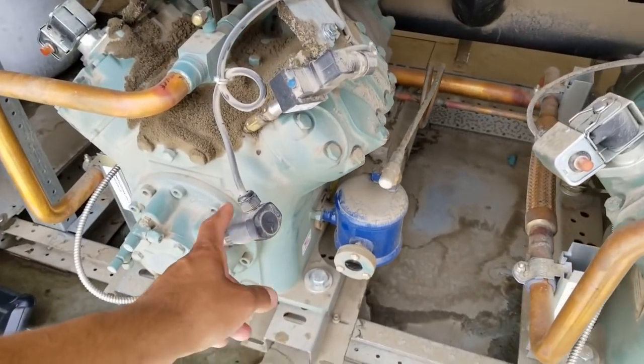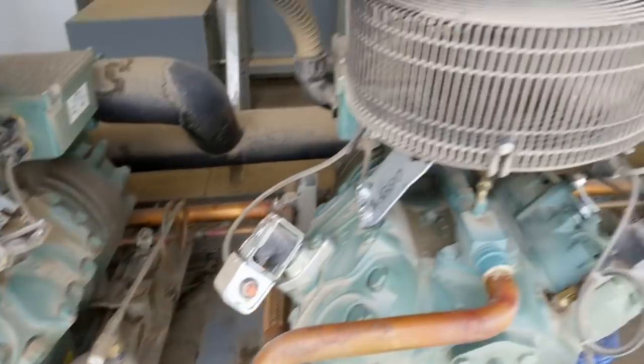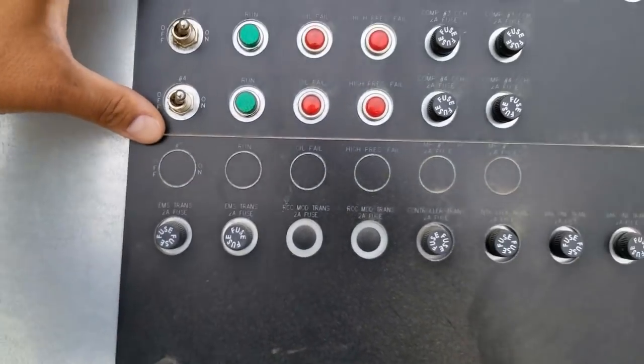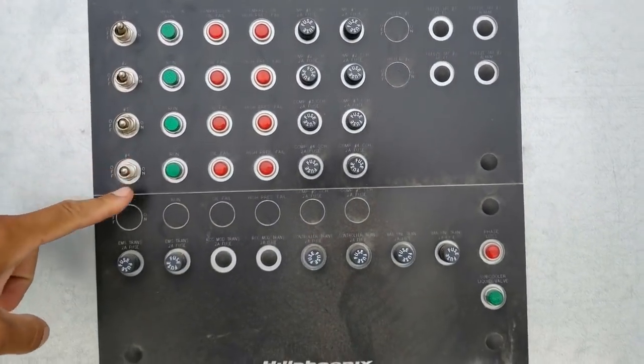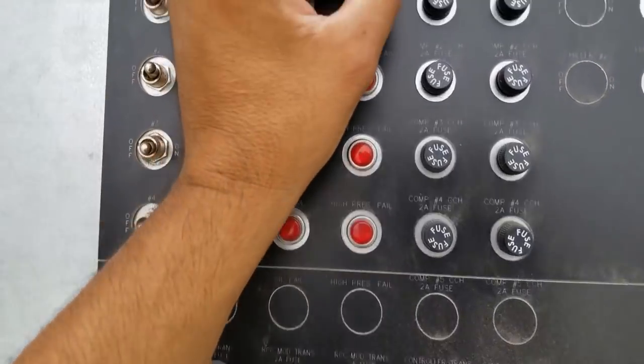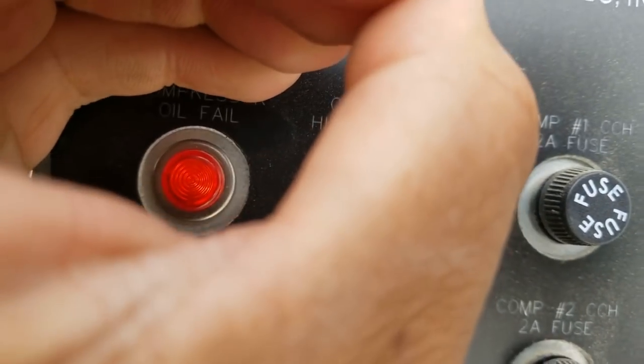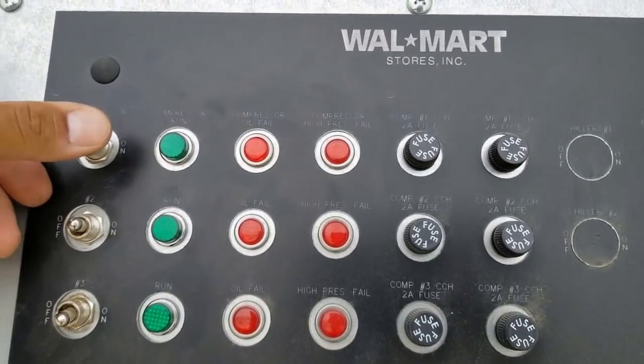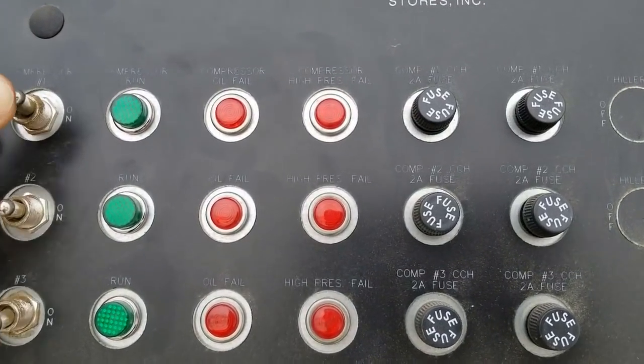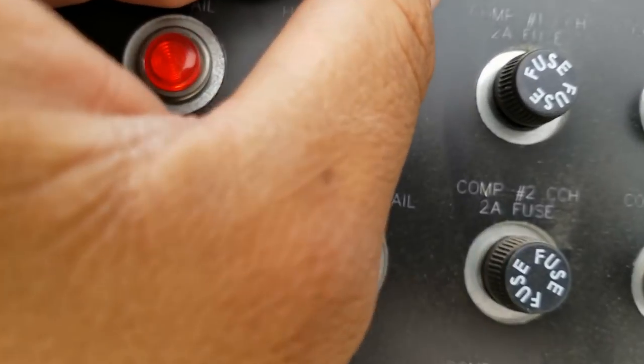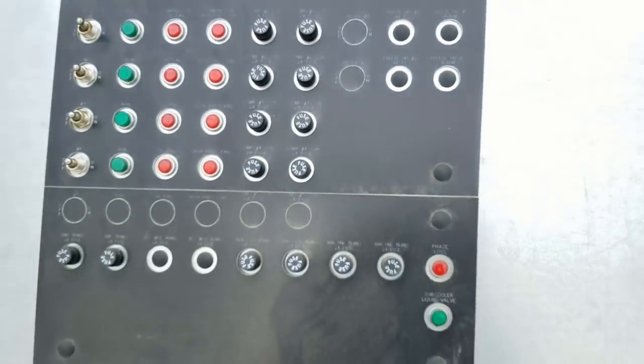Alright, so the way to reset these oil fail controls is you have to reset the power to those things. And here's my toggle switches for all 4 compressors. And this one here is lit up. See the difference? That one's lit up. So in order to do that, you just turn the power off and you just turn it back on. The light will go away, and then my compressor should start up. And by the way, we turn it off a little longer. Maybe I didn't turn it off long enough.